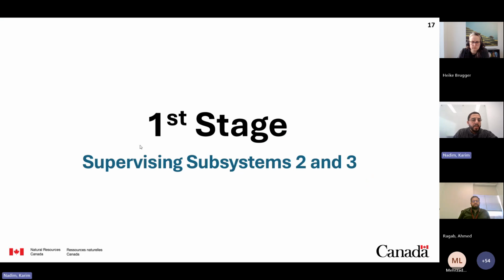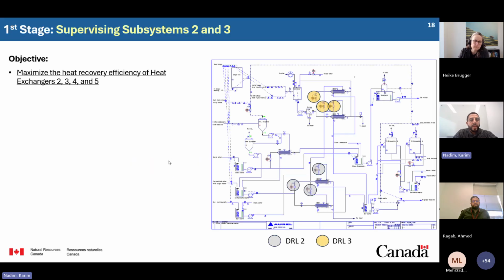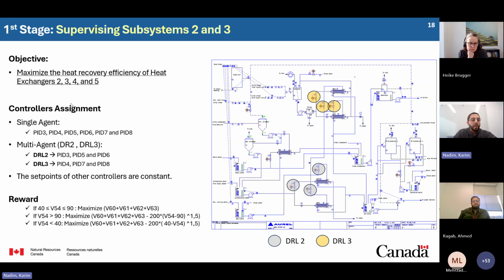Let's go to the results of the first stage, where we are supervising subsystems 2 and 3. As shown in the figure, the objective here is to maximize the heat recovery efficiency from heat exchangers 2, 3, 4, and 5. For the controller assignment, we compare the performance of the single agent and the multi-agent. The single agent controls all 6 PID controllers simultaneously, while for the multi-agent, we create 2 agents, one for each subsystem.